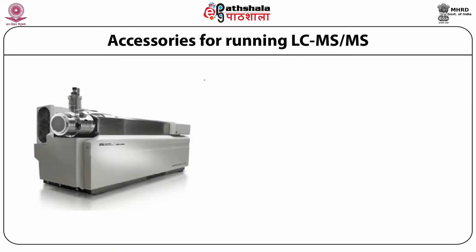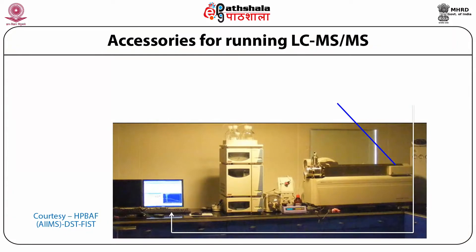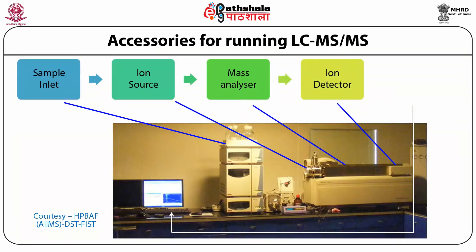The LC-MS/MS triple quadrupole tandem mass spectrometer shown here is the AB Sciex instrument in the speaker's laboratory. It requires nitrogen, zero air, compressed air, a high vacuum pump, HPLC, and a sample infusion assembly. The instrument includes a sample inlet (HPLC), an ion source — electrospray ionization, APPI, or APCI — which converts liquid-state ions to gaseous state, a mass analyzer housing all three quadrupoles, an ion detector, and a microprocessor for data collection and interpretation.